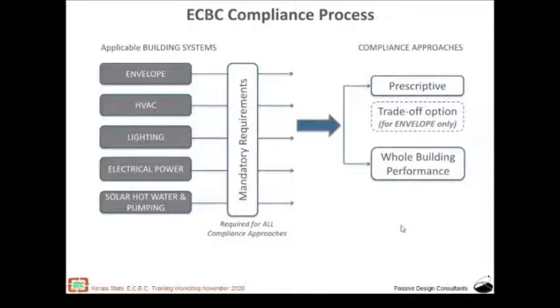The whole building performance approach allows a trade-off not only within the HVAC section, but also between different sections of ECBC. For example, if a project is not able to meet a certain requirement of envelope, neither by prescriptive nor by the trade-off method, then the project team can use the whole building performance method such that the HVAC section, the air conditioning or the lighting, compensates for that additional energy consumption due to envelope and ensures that there is no more energy consumption than the baseline case.